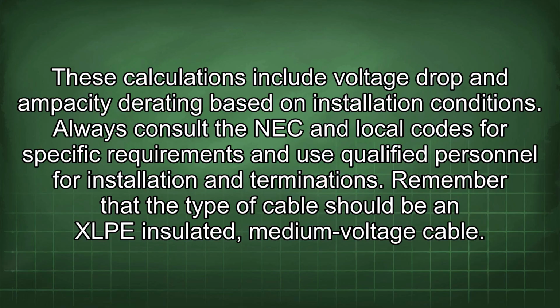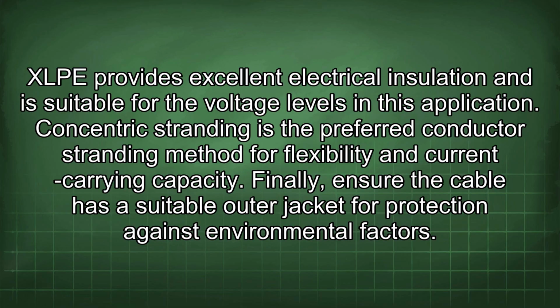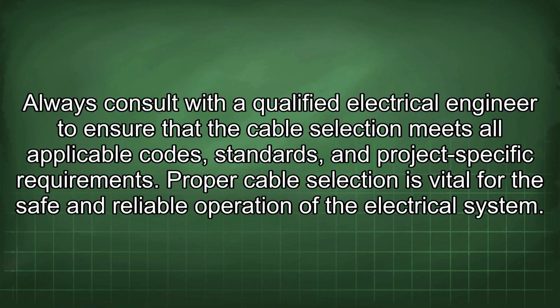Remember that the type of cable should be an XLPE insulated, medium-voltage cable. XLPE provides excellent electrical insulation and is suitable for the voltage levels in this application. Concentric stranding is the preferred conductor stranding method for flexibility and current carrying capacity. Finally, ensure the cable has a suitable outer jacket for protection against environmental factors. Always consult with a qualified electrical engineer to ensure that the cable selection meets all applicable codes, standards, and project-specific requirements. Proper cable selection is vital for the safe and reliable operation of the electrical system.